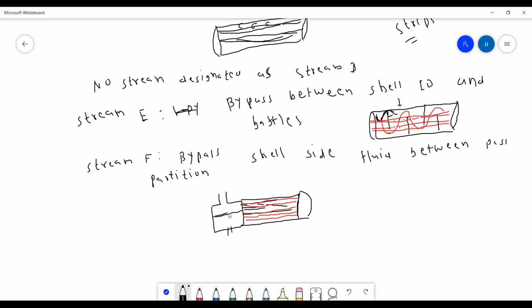Now this is the tube side pass partition. The fluid enters from the top, which enters into this tube in the first pass and in the second pass. In the second pass, it also passes in the tubes and leaves from the bottom. But if there is some gap here, for example, this is the pass partition gap for tube side, some of the fluid may also bypass between these gaps. This is the shell side, tube side bypass.